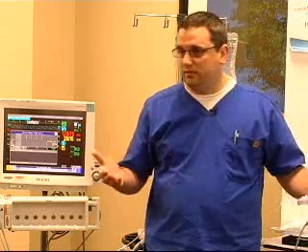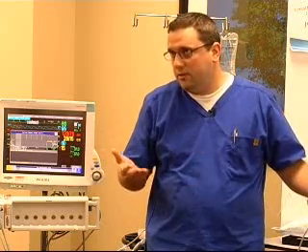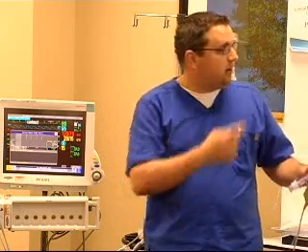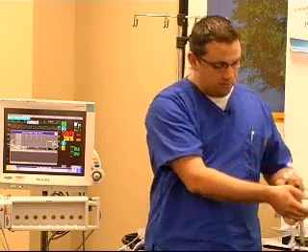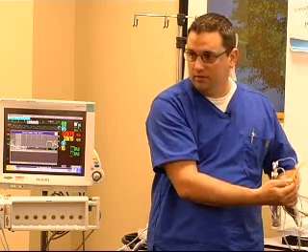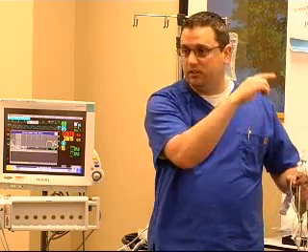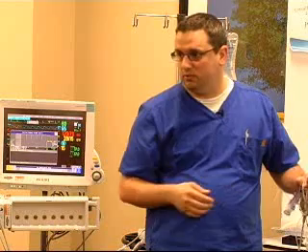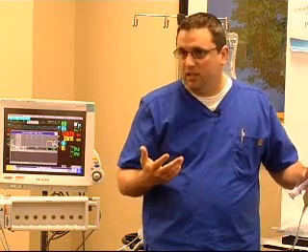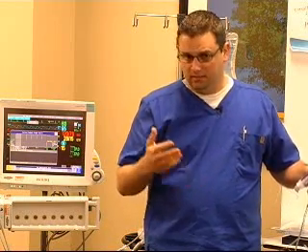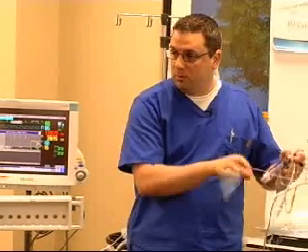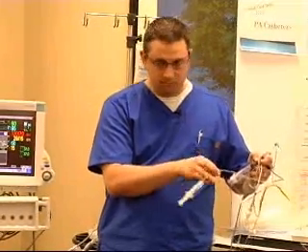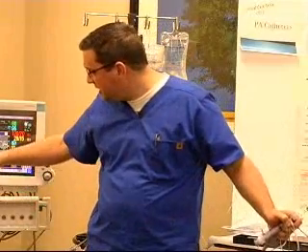And if you happen to have lost that, now what do you do? These are Edwards products, and on their website they actually have that conversion scale right there, and you can match the model number on here directly to that chart, and it will tell you which computation constant you should be using. Okay? Not that we really use a whole lot of different Swans, except for this one, or without an RV port, sometimes from Cath Lab. So anyway, you're going to confirm that.